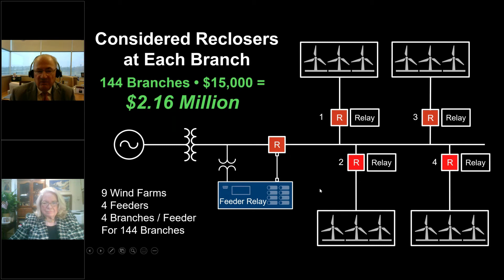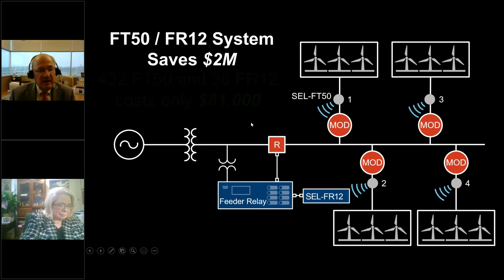So they realized they could use fault transmitters. When a fault occurred, they'd know right away which branch it was on. The relay still trips the whole farm, but then they know which motor-operated disconnect to automatically open to restore the scheme. This saved $2 million—instead of spending over $2 million, they spent $80,000.